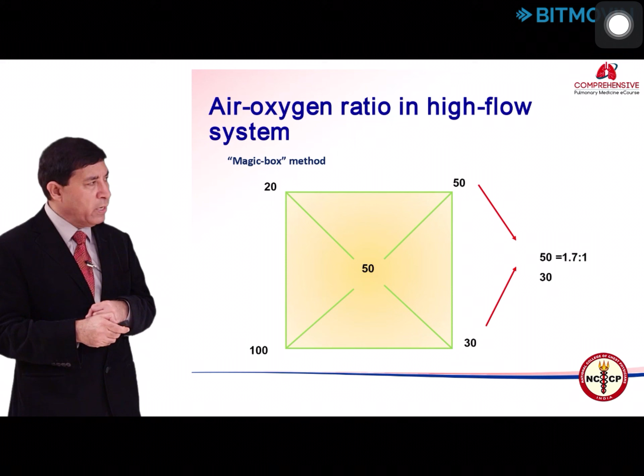So to generate 60 liters of flow, if you see this entrainment ratio, then that means if you provide 50 liters of oxygen, you will get around 30 liters of air. So it will become around 80 liters. When you are using the high flow system, it is very important to calculate the flow requirements of the patient, and then you calculate the entrainment ratio, and then accordingly you adjust the oxygen flow from the source, and then you are going to get the flows accordingly.